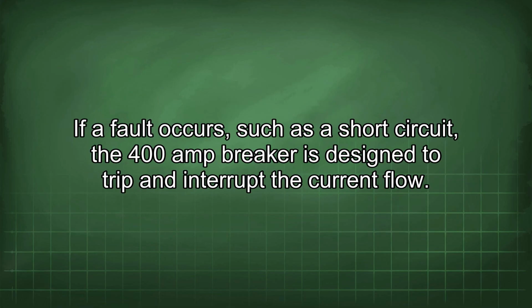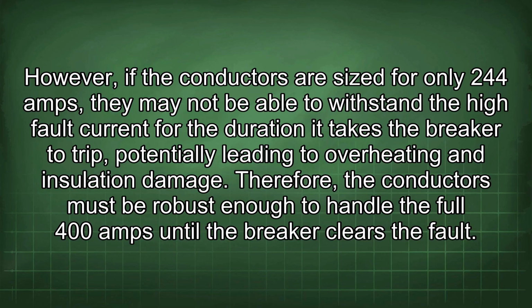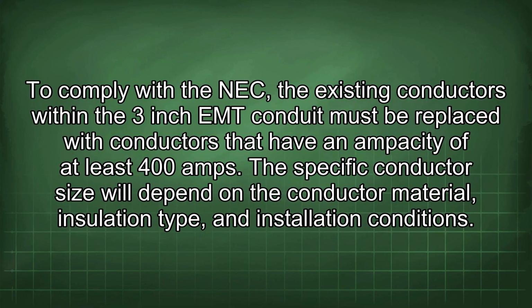If a fault occurs, such as a short circuit, the 400 amp breaker is designed to trip and interrupt the current flow. However, if the conductors are sized for only 244 amps, they may not be able to withstand a high fault current for the duration it takes the breaker to trip, potentially leading to overheating and insulation damage. Therefore, the conductors must be robust enough to handle the full 400 amps until the breaker clears the fault. To comply with the NEC, the existing conductors within the 3-inch EMT conduit must be replaced with conductors that have an ampacity of at least 400 amps.